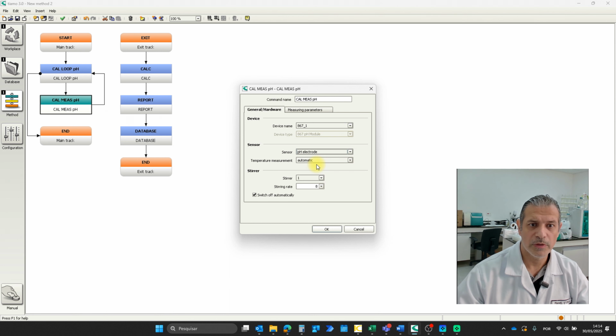Now the CAL MEAS pH box. Here we select our equipment, the 867. The sensor, the pH electrode, is set by default, but you can create a new one. I'm going to show you how to create a new electrode. Going to configuration, and here in the sensor window, hit edit, new pH electrode. Let's call this electrode. The order number is the part number 60260-010. If you want, you can add the serial number, the device, for example, here, and the measuring input. You can monitor your sensor. There are a lot of other things that we are not going to see now. They're not important for the calibration method.